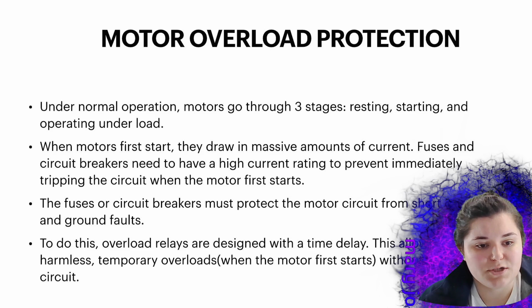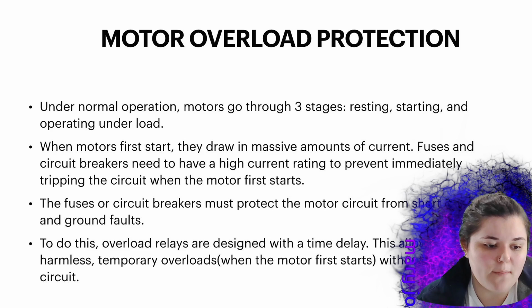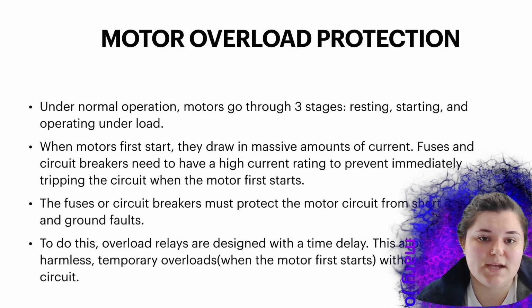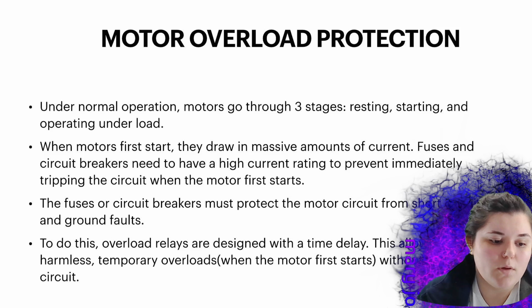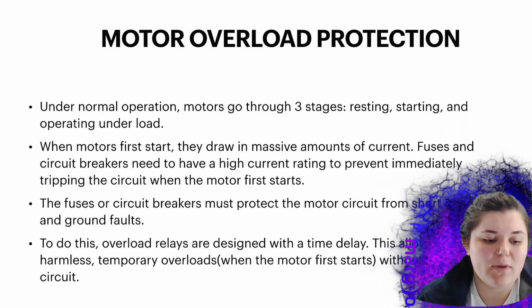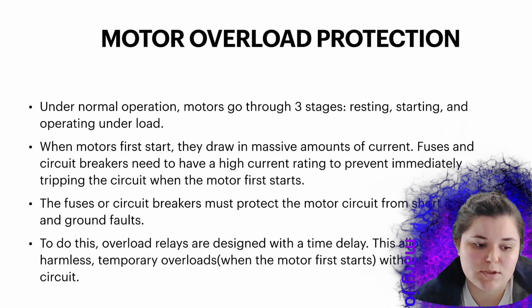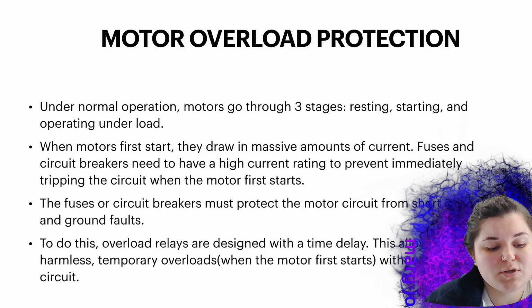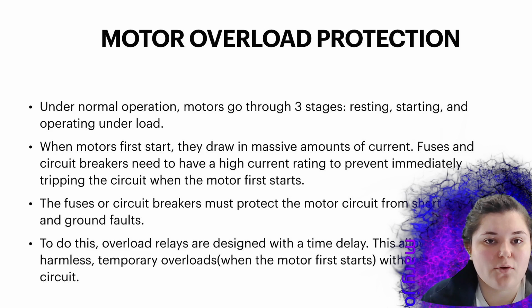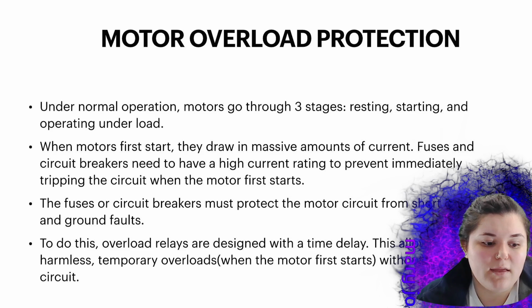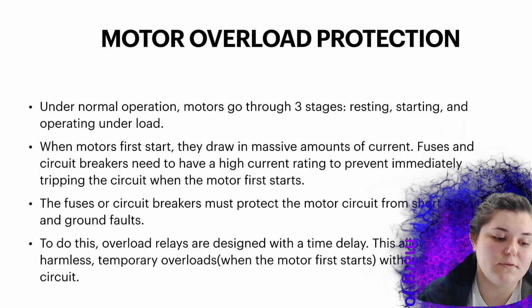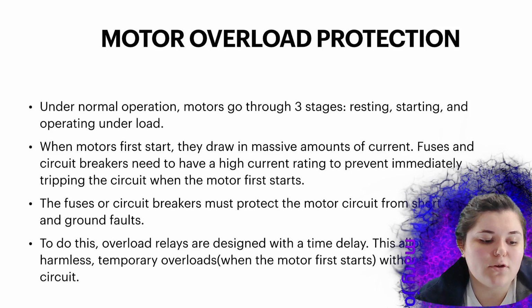Motor overload protection. Under normal operation, motors go through 3 stages, and that's going to be resting, starting, and operating under load. When motors first start, they draw massive amounts of current. Fuses and circuit breakers need to have a high current rating to prevent immediately tripping the circuit when the motor first starts. The fuses or circuit breakers must protect the motor circuit from short circuits and ground faults. To do this, overload relays are designed with a time delay. This allows the harmless temporary overloads when the motor first starts, without tripping the circuit.